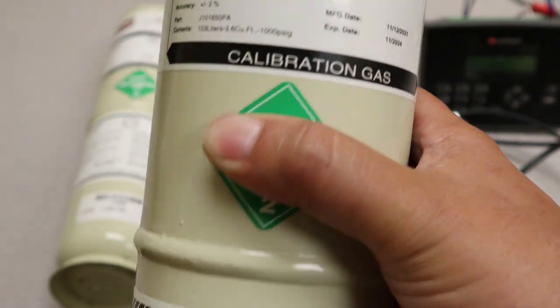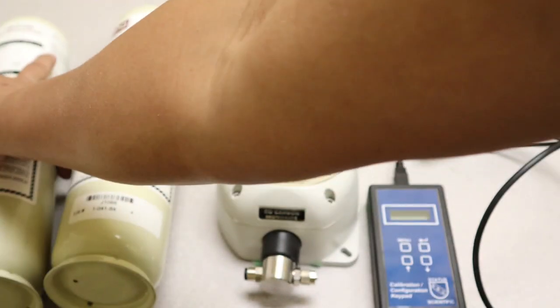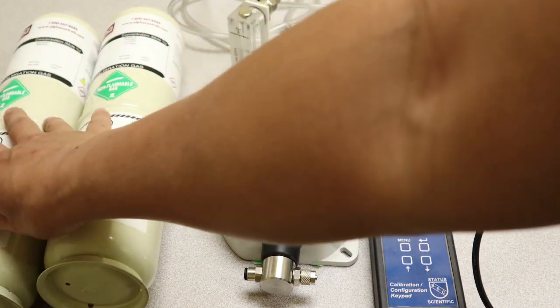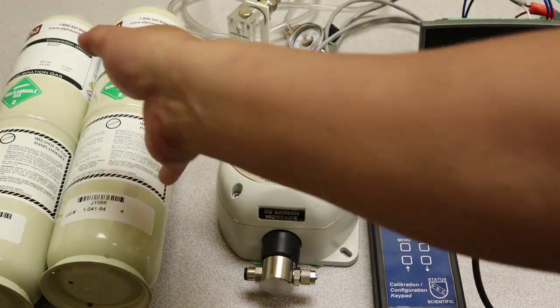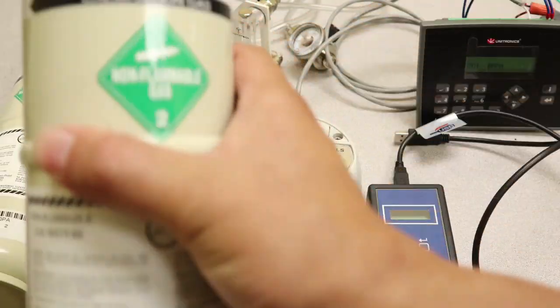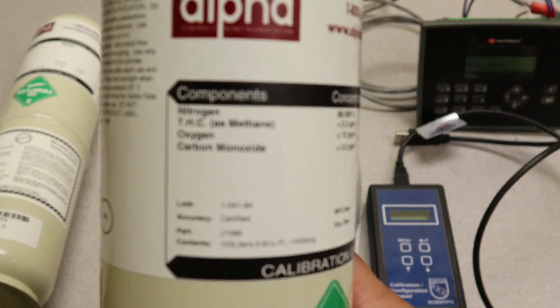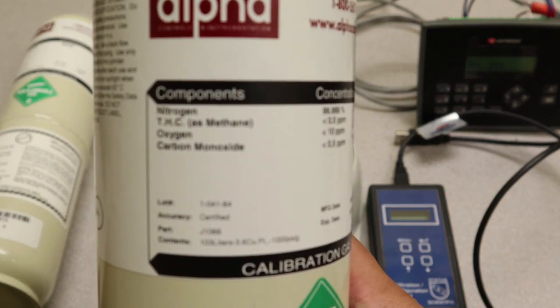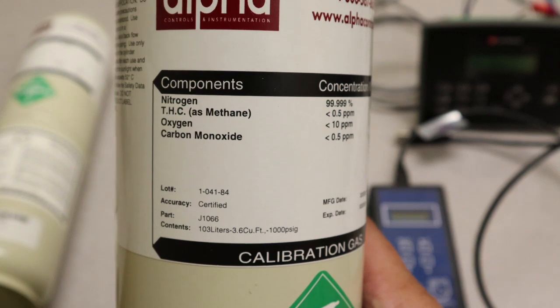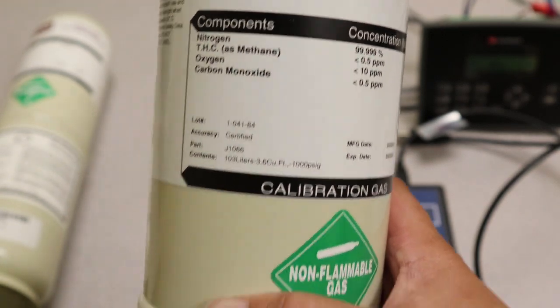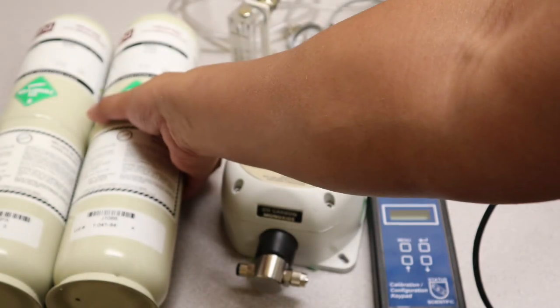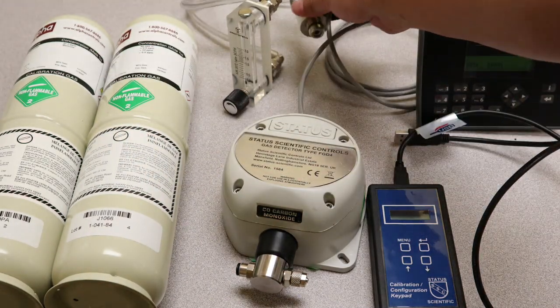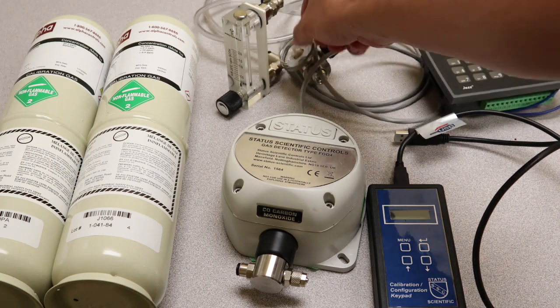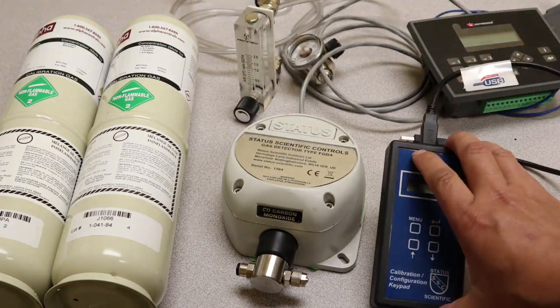It doesn't have to be 50 ppm. It can be done with 20 ppm that are commonly used as well, and we'll talk about that during the calibration instruction. The other component that you're going to need is a bottle of nitrogen. So we have a bottle of nitrogen right here. The nitrogen is going to be our zero gas, meaning that it's going to be the base for our calibration at the 0 mark. Another thing we're going to need is a bottle regulator, a flow meter, and a keypad.